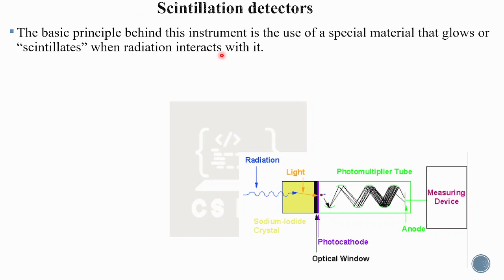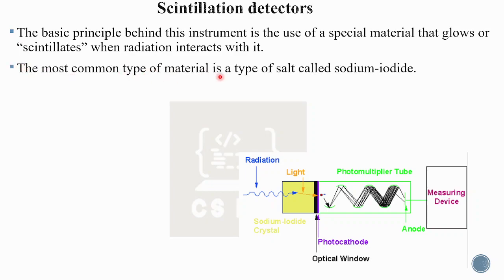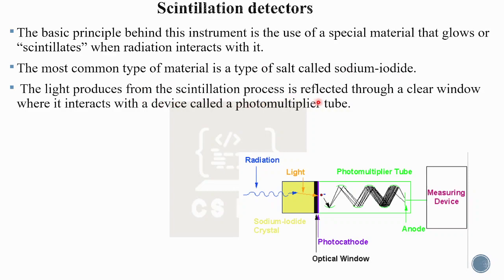The basic principle behind the scintillation detector is the use of a special material that glows or scintillates when radiation interacts with it. The most common type of scintillation material is a type of salt called sodium iodide. When radiation strikes the sodium iodide, it glows or scintillates. The light produced from the scintillation process is reflected through a clear window.